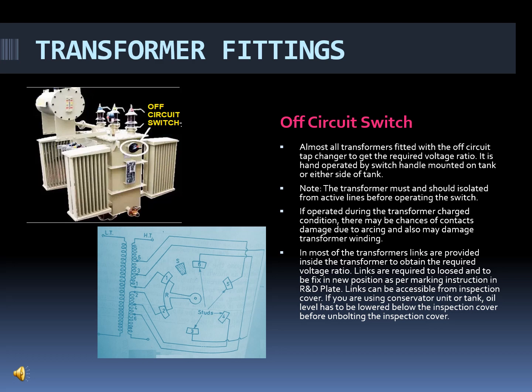In most transformers, links are provided inside the transformer to obtain the required voltage ratio. Links are required to be loosened and fixed in the new position as per the marking instruction on the R&D plate. Every R&D plate has an off-circuit switch marking plate. In this plate, they have mentioned the position numbers. As per the position number, we have to loosen the links of the off-circuit switch and fix them in the new position. The links can be accessed from the inspection cover. Transformers having an inspection cover allow the links to be visible and accessed from it.